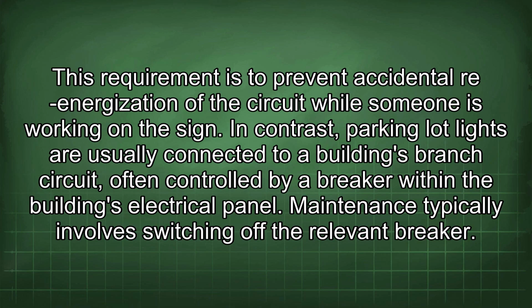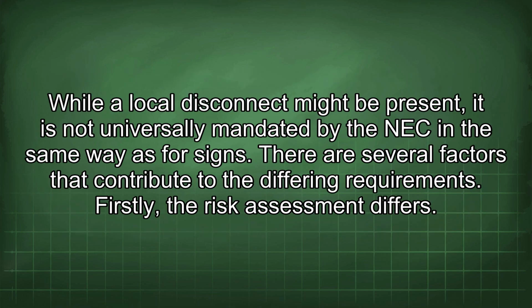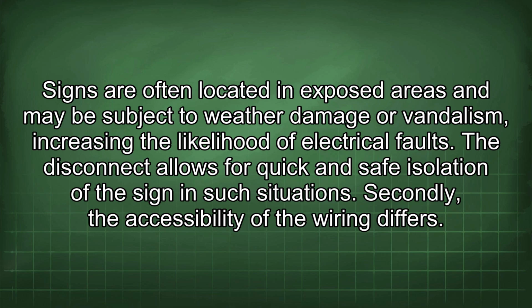In contrast, parking lot lights are usually connected to a building's branch circuit, often controlled by a breaker within the building's electrical panel. Maintenance typically involves switching off the relevant breaker. While a local disconnect might be present, it is not universally mandated by the NEC in the same way as for signs. There are several factors that contribute to the differing requirements. Firstly, the risk assessment differs. Signs are often located in exposed areas and may be subject to weather damage or vandalism, increasing the likelihood of electrical faults. The disconnect allows for quick and safe isolation of the sign in such situations.